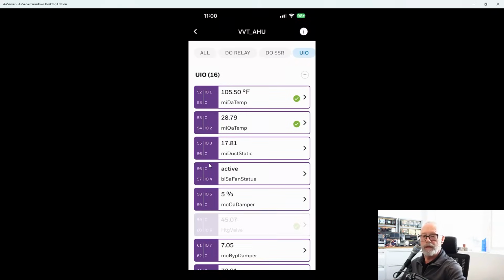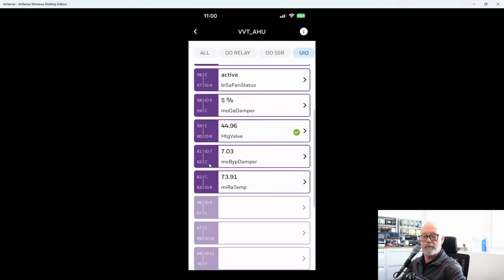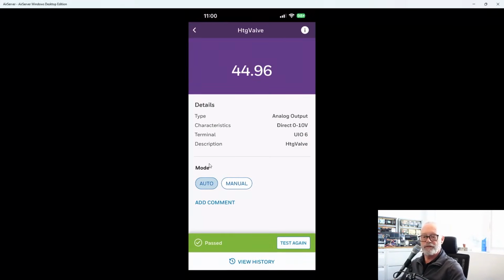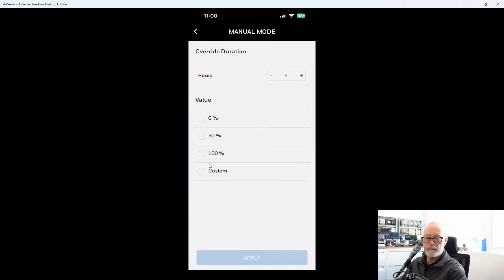Over on the UIO, we could come in here and go to my heating valve, go to manual, and then you have the choice of going 0, 50, 100%, or you can put a custom value in there to whatever you'd like. Then you have this override duration in hours. The lowest you can get is 1 hour.